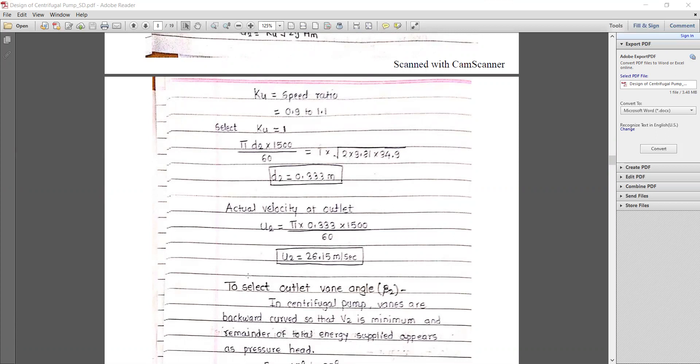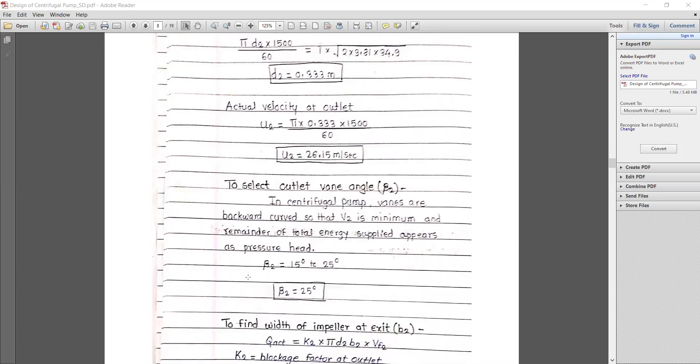Note: this outer diameter d2 cannot be modified to a standard value because changing the diameter would alter the angular velocity and all related parameters. The actual peripheral velocity at outlet: u2 = π × 0.333 × 1500/60 = 26.15 m/s.